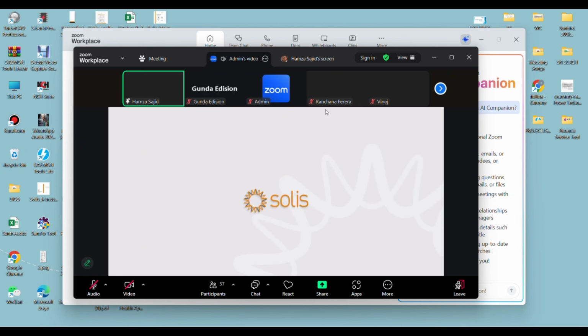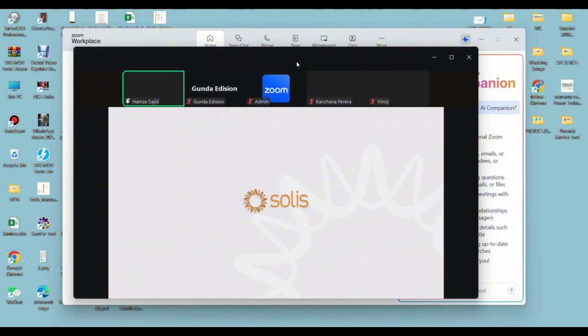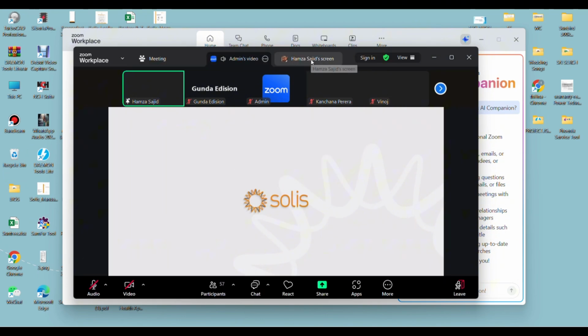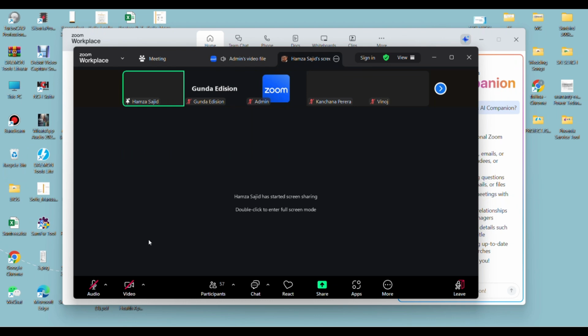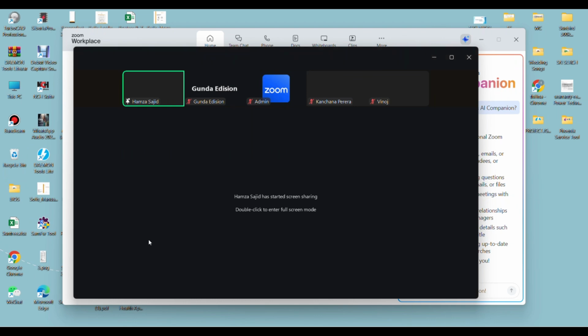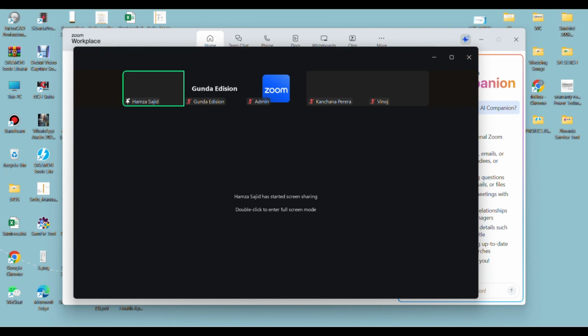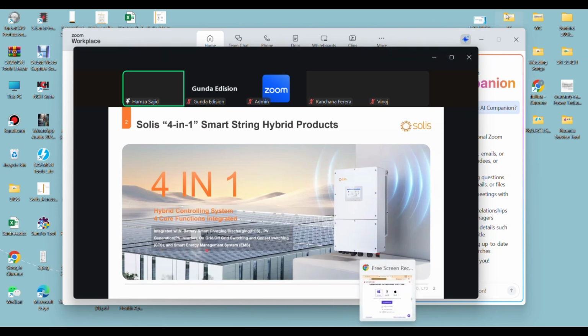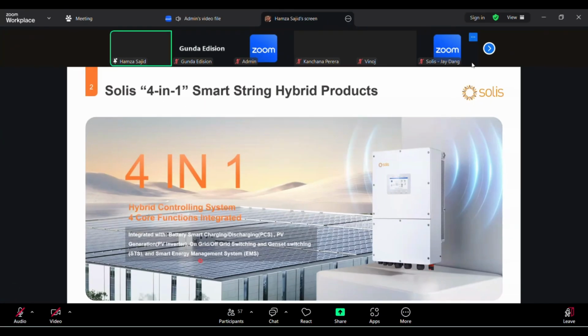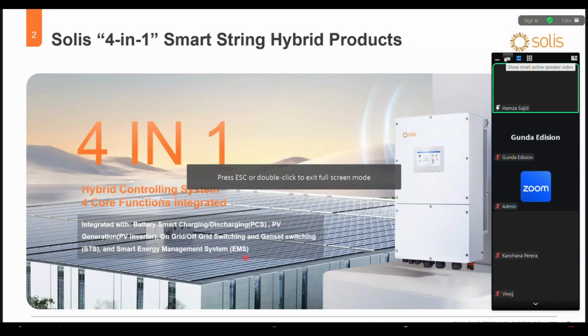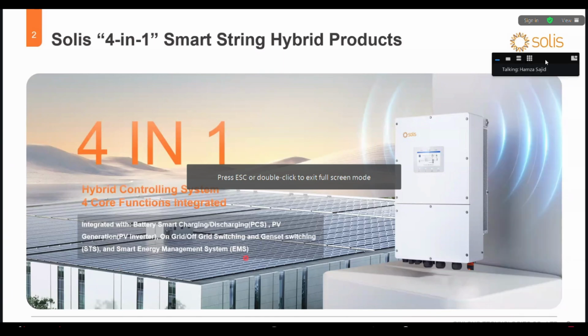Okay. PCS means power control system. That means it is utilized for charging and discharging of the battery. Then you have the PV generating system, that is the PV inverter, which is already inside the inverter. On-grid and off-grid switching or genset switching is done by the STS, static transfer switch. So we already have this feature available. And the last and most powerful thing is the smart energy management system, that is called EMS. We already have the system.